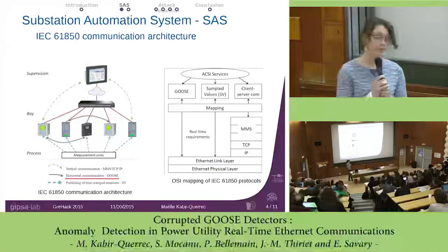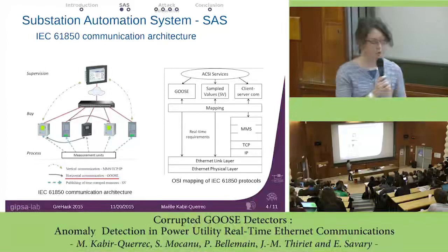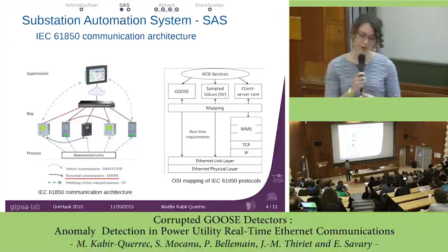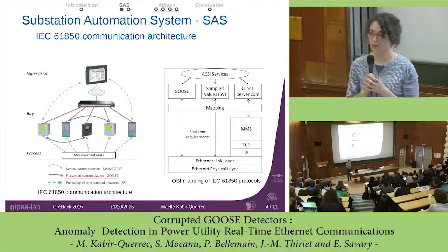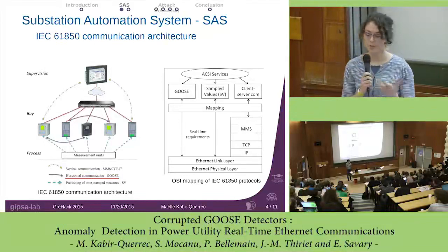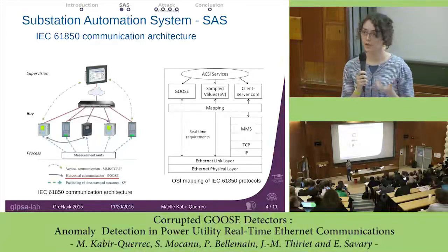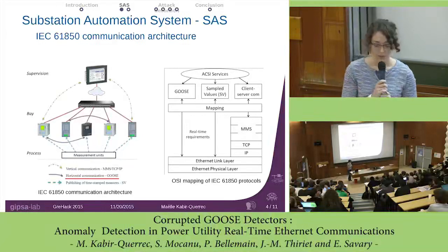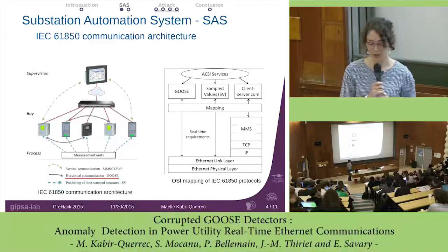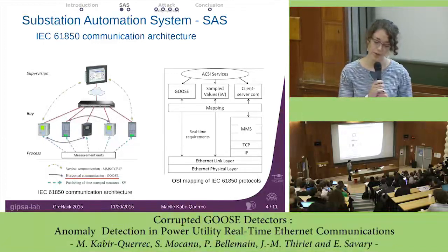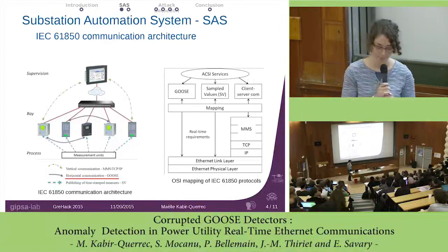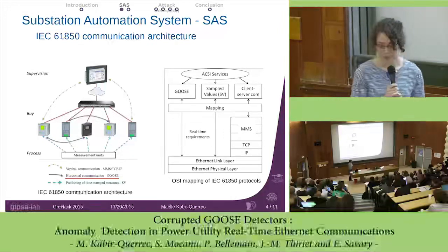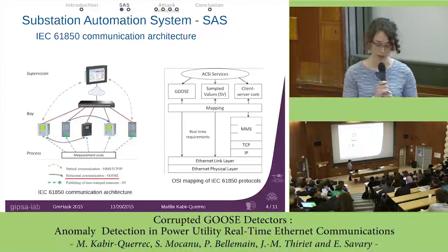So I will present the system. The system is the substation automation system. It's basically all the systems and networks involved in automation operations of the power grid. The communication architecture used in such a substation automation system follows IEC 61850 requirements. And here is a typical IEC 61850 communication architecture.